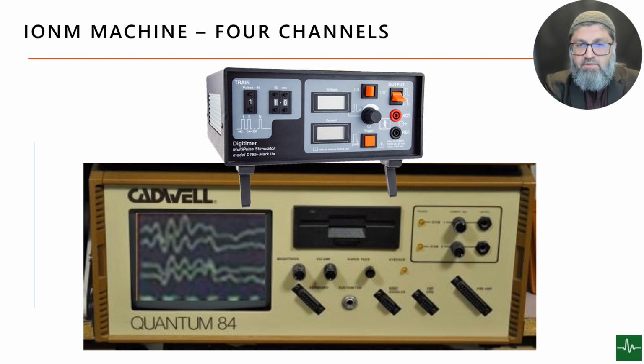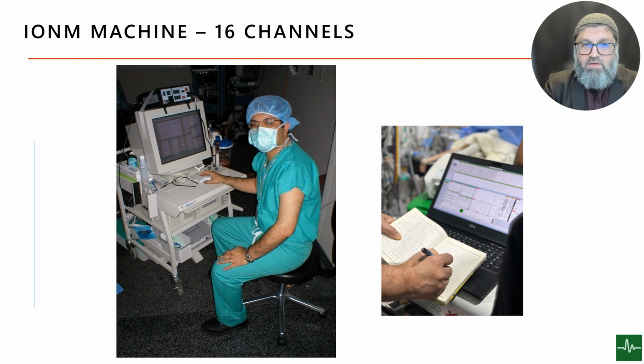So we used the Digitimer, connected through an external cable, and every time you stimulate motors from the Digitimer, we record from our IONM machine. This is me in Philadelphia about 20 years ago, in early 2002, 2003. This was a 16-channel machine, and this Bravo machine was also not approved for motor evoked potentials. So we had the Digitimer attached and connected through a cable, and we used it for training purposes and monitoring purposes.